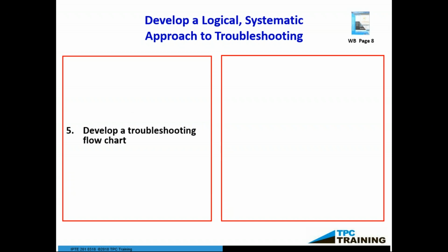I want to develop a troubleshooting flow chart. Over the years I've thought about this in different ways, but just a regular flow chart: yes, go forward here; no, go down and check this. Think about how your machine's supposed to work. Get it logical: I press the button, the pump turns on, the fluid starts coming out, the drill starts turning, the sequence of operation. Put that together in a flow chart.